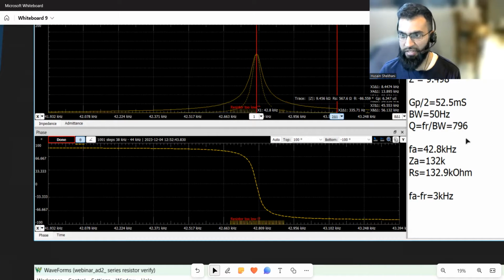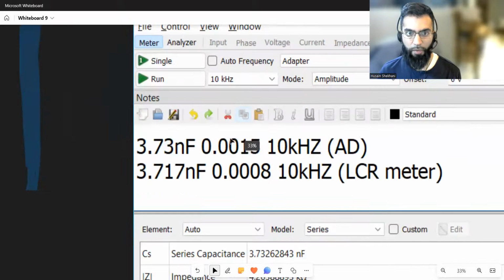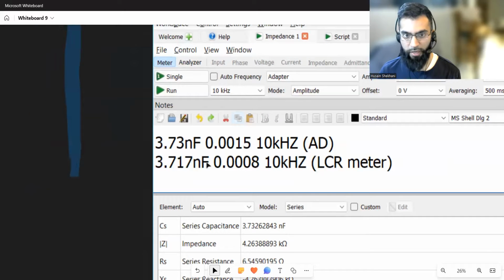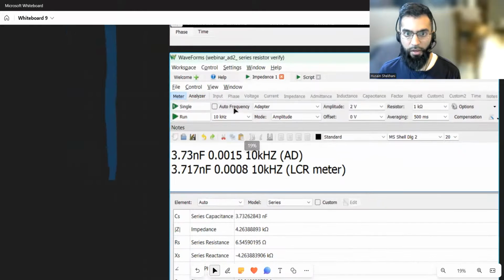So the Q factor ended up being 796. I did a similar thing for anti-resonance, and I wrote down the frequency between resonance and anti-resonance. And that's pretty much what you need for analyzing a transducer. I went back to the meter mode because we do want those 10 kilohertz LCR values. So when I ran the Analog Discovery, this is what I got for the capacitance and the dielectric loss, 0.0015.